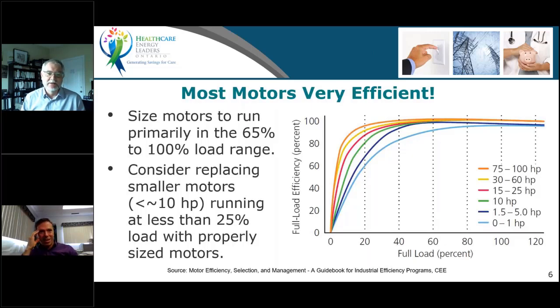So I'm going to start off with the motors. I want to say a few words about motors because motors are part of the system. Typically, you want to size motors to run in that 65 to 100% range. You don't want to size them way over range, especially small motors. In the 65 to 100% range, the efficiency of most motors is relatively flat. It doesn't change dramatically, but because a motor has fixed losses, and the smaller the motor, the greater the fixed losses due to certain aspects of the design, the efficiencies drop off when you get down in that 25% range.